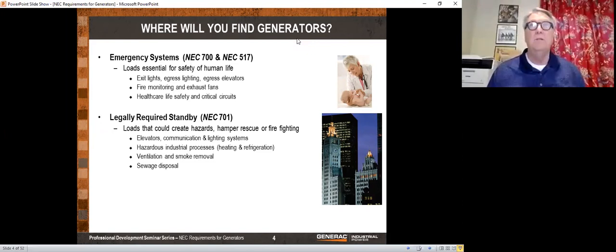So pretty much any generator on a hotel is likely to be an emergency generator because they're using it for egress out of the building. And of course, healthcare. Now, all of healthcare doesn't require an emergency generator, just your life safety and critical circuits. Now, the second kind of generator that has different codes is your legally required standby.